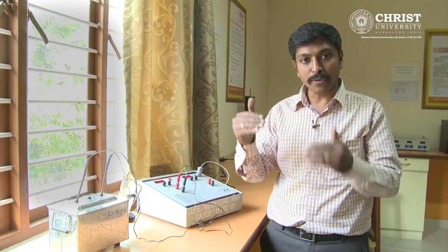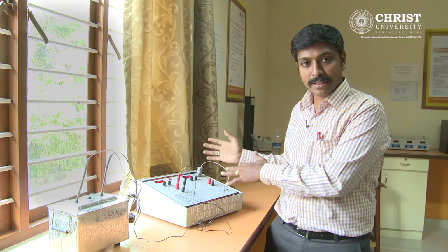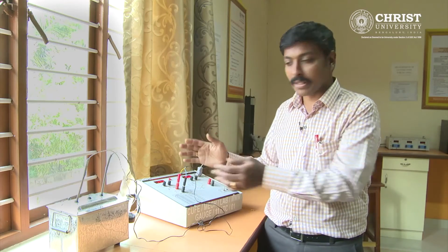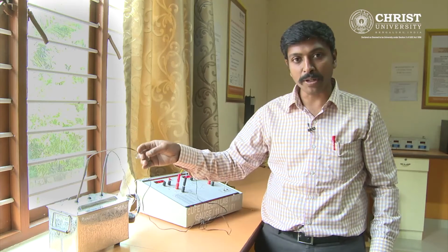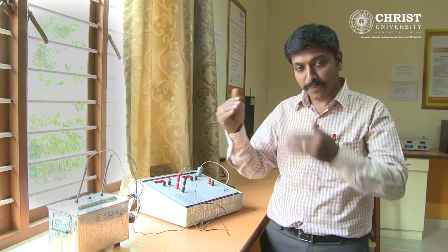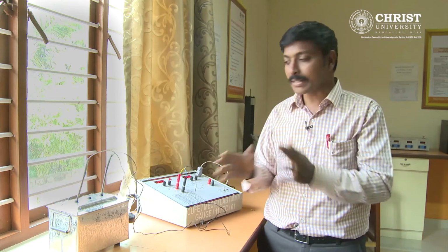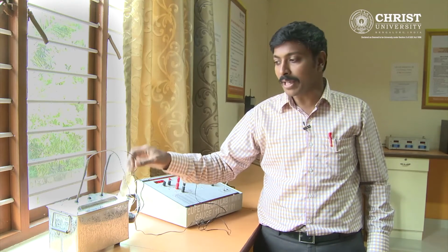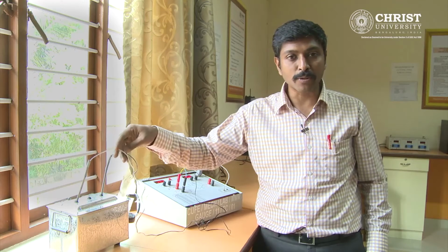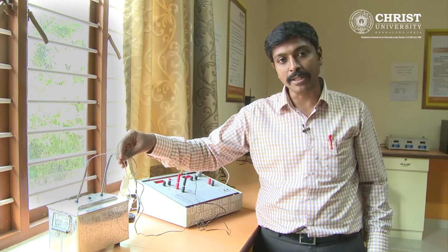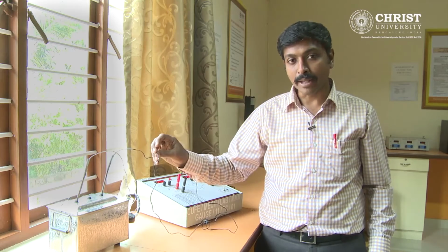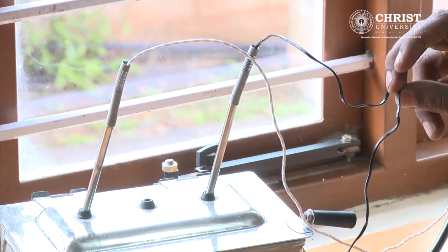So every 10 degrees you have to find out what is the reading on the equipment on the right side and what is the equipment on the left. That is our thermocouple, which is the variable equipment, and how much it is going to predict. The difference between these two will help you understand how far my thermocouple has the efficiency inside. Because I believe this is the ideal equipment, there is no chance of any kind of mistake in its measurement. So I suspect the black color thermocouple is going to have some error inside.